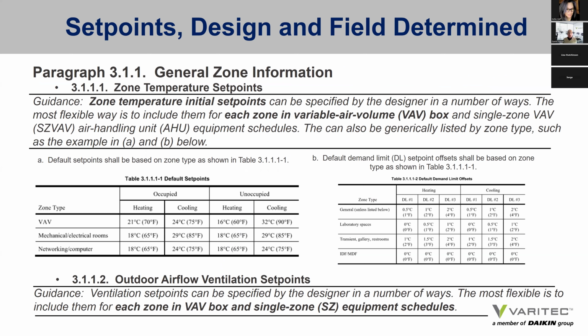So the first thing that needs to be conditioned is the temperature set point. The guideline actually gives guidance on how to write zone temperature set points. In fact, it gives you the values that are displayed here. So the guidance in the guideline calls out that zone temperature initial set points can be specified by the designer in a number of ways.